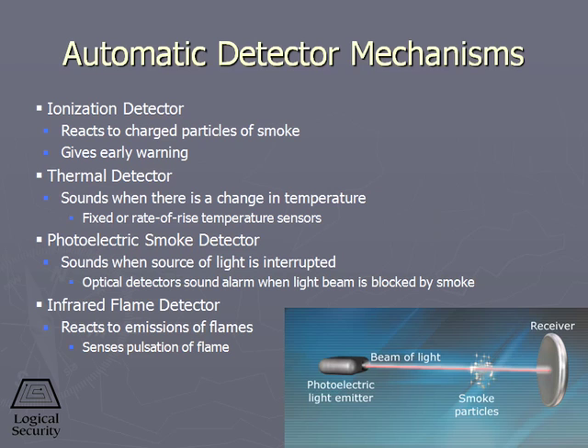With fire detection, there are generally four types of fire detectors. You need to know all four of these. The first, and probably the most prevalent, is the ionization detector. An ion is a positive or negatively charged particle or atom. Atoms by default have a balance of protons in the nucleus and electrons orbiting around the protons. So these are not ions, these are balanced atoms. However, in the presence of high temperature and chemical reactions, we tend to cook off or attract additional electrons, causing an imbalance in the charge. The imbalance in this charge on an atom is called an ion. Again, in the area of a fire, ions increase. And so we detect these imbalanced atoms and use this as our detection mechanism.